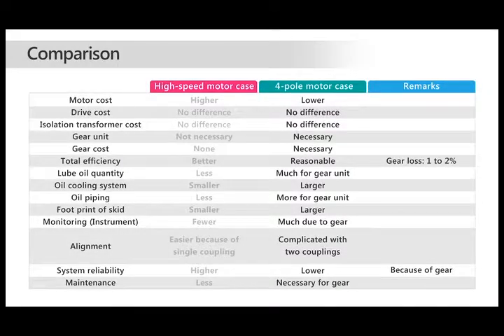Here are some comparisons between our high-speed motors and regular 4-pole motors. While a high-speed motor itself costs more than a regular 4-pole motor, a relevant drive and isolation transformer cost the same, as the motor output is the same. As you can see on this table, high-speed motors have a number of advantages due to the gearless configuration. To start with, costs related to the gear unit and its operation are non-existent. Total efficiency is better as there's no gear loss. You need less lube oil, a smaller oil cooling system, less oil piping, a smaller footprint of skid, and fewer monitoring instruments. Alignment is easier thanks to single coupling. System reliability is higher and less maintenance is required as you do not have to worry about the gear.